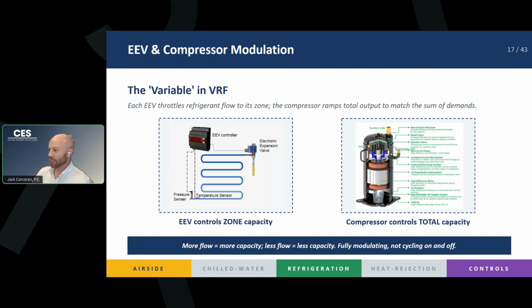However, as each zone starts to get satisfied, those electronic expansion valves start to close. Once one, two, three, four zones start to taper down the amount of refrigerant they need, you've got to slow down your compressor too, right? So your 20-ton system can actually ramp down, as your compressor speed slows down, to get to a 10-ton, a 12-ton, or a 14 tons of actual demand load, right? And so these two components and sides of the refrigeration cycle work together in order to meet your exact demand. And that's the powerful part of VRFs, right? So more refrigerant flow means more capacity. Less refrigerant flow means less capacity. And your EEV and your variable speed compressor work together to make sure that every zone gets the correct amount of flow, depending on how much cooling or heating it needs.